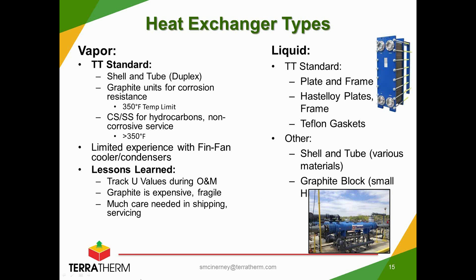Just quickly stepping to lessons learned here, one thing that we've added to a lot of our O&M data management is to track U values. And those that have taken heat exchange back in the day, U value really is sort of an indicator of the ability of an exchanger to transfer heat. And when U values deteriorate, that's an indication that the exchangers themselves may be fouling, or there's a change in process flow conditions through the unit. And when those U values deteriorate, it's time to think about service or a closed system inspection.